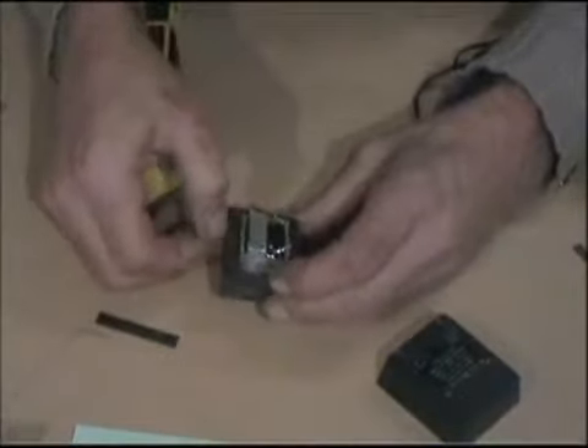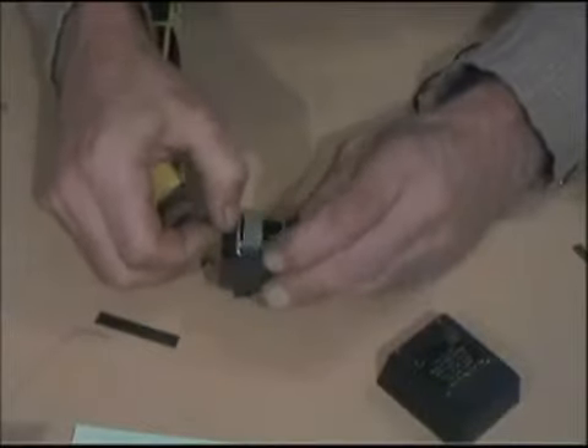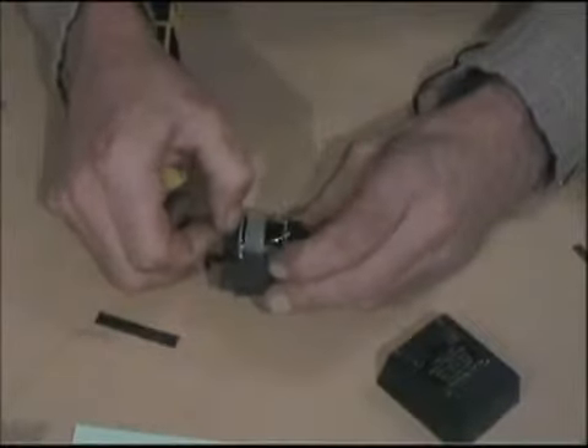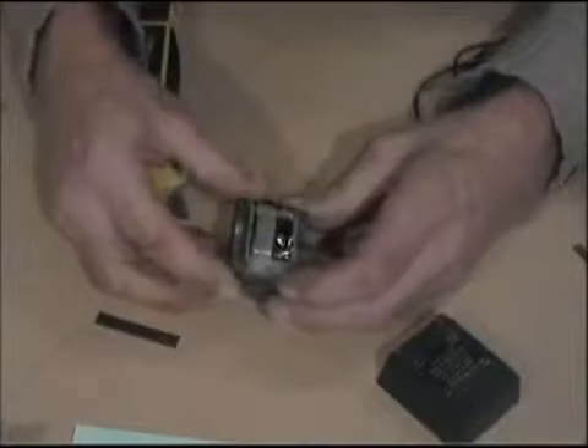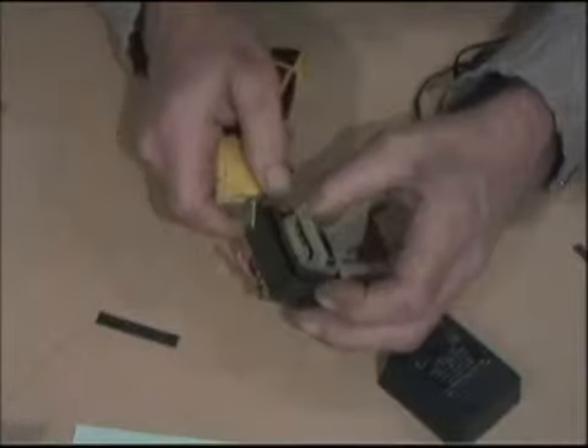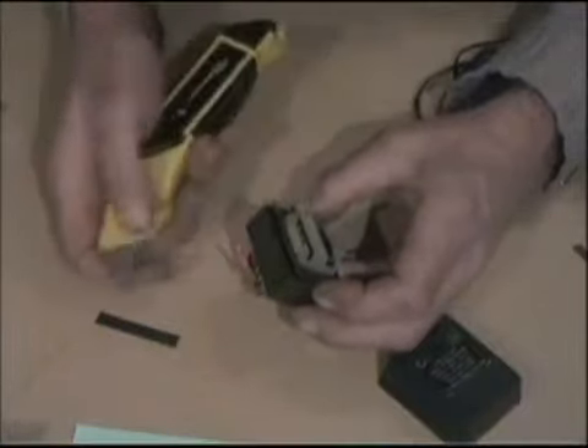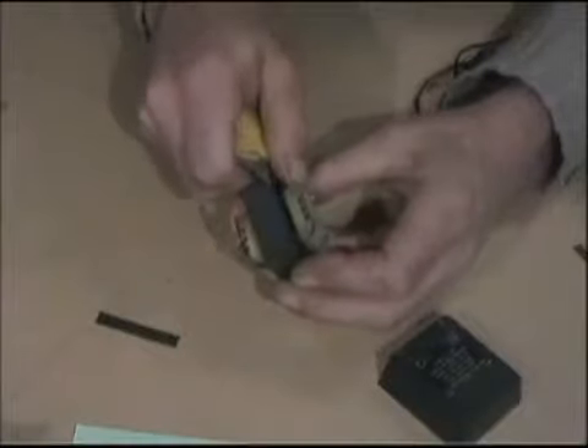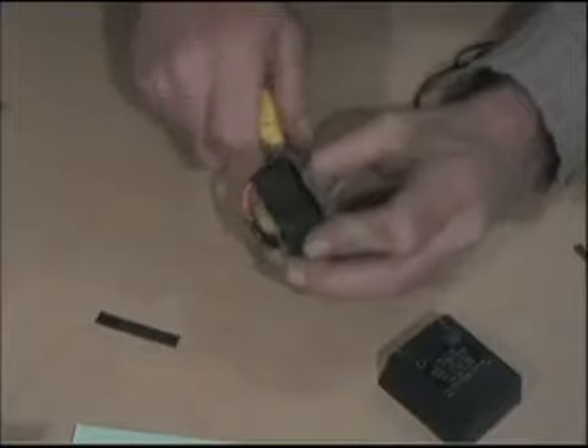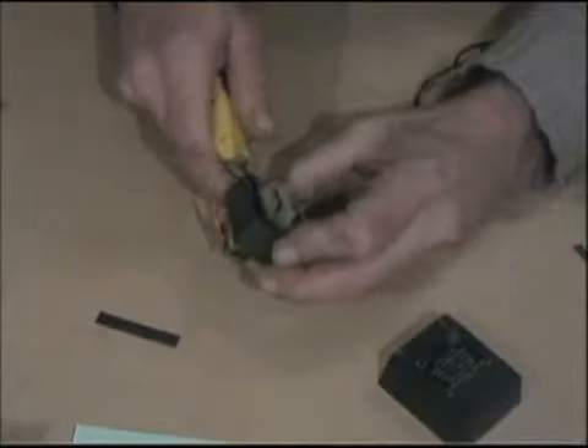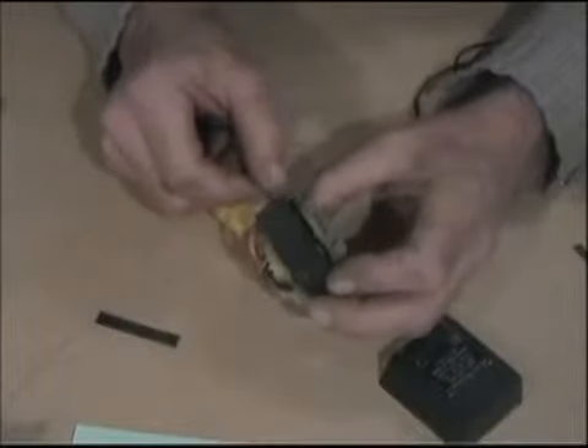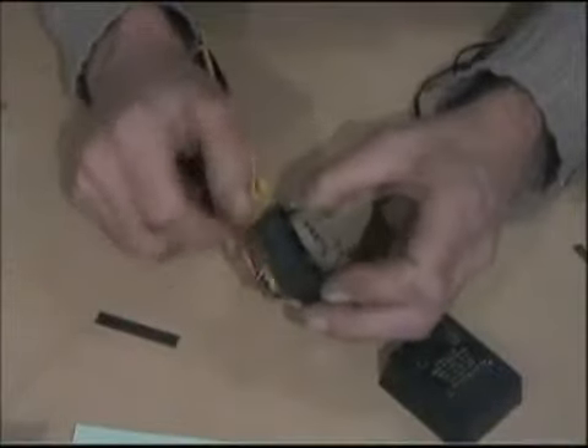...you can then get some pliers on there, and as you notice, it's starting to fall apart already. You start pulling these laminations out - you might need decent pliers or pipe grips to get the first one out, but once you get going, you work your way down, and as each of the E-I laminations comes out, you just gently ease them. You don't have to bend every one, but once you get a move on, they'll come out fairly easily.